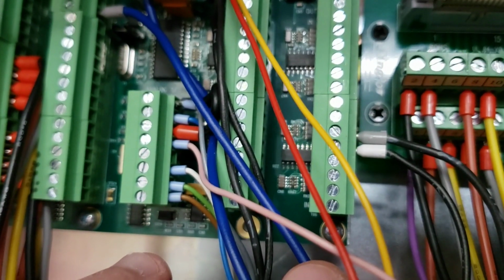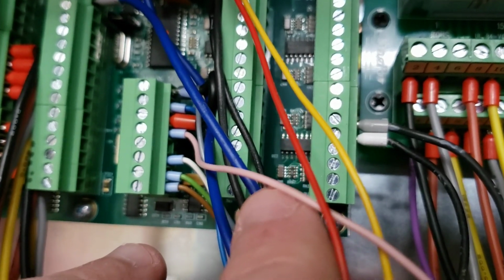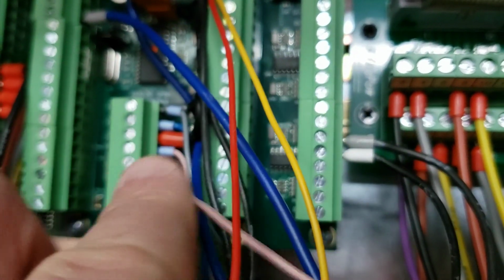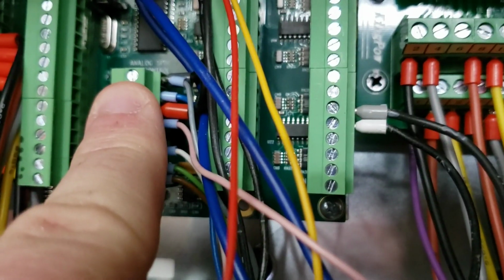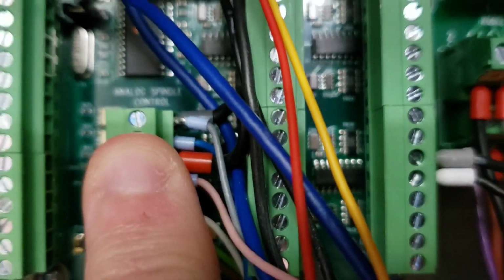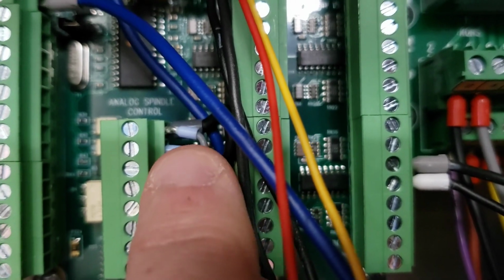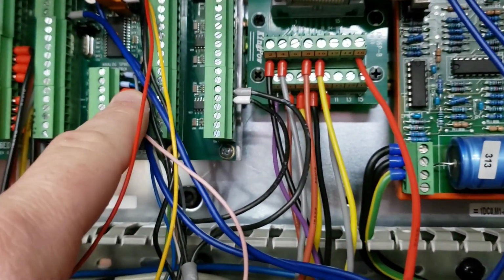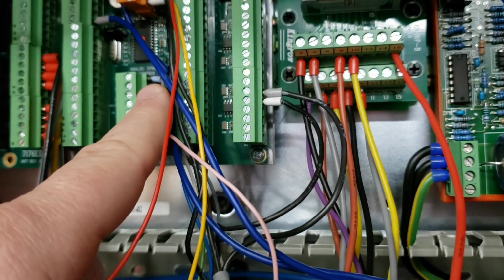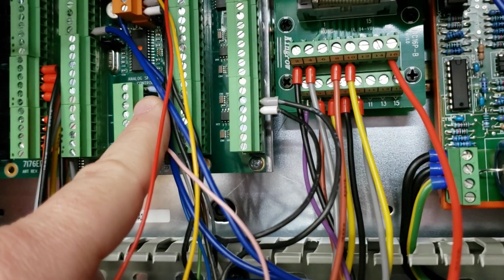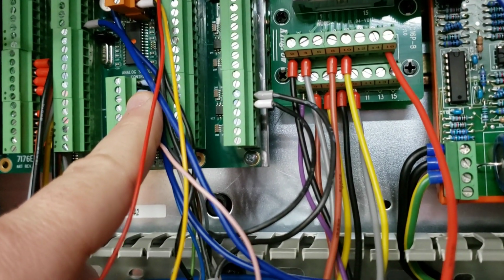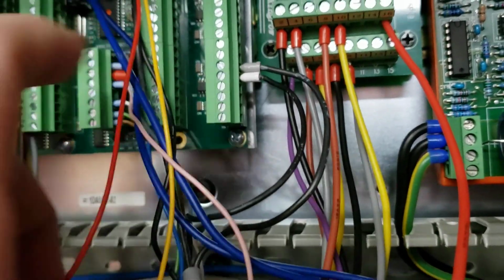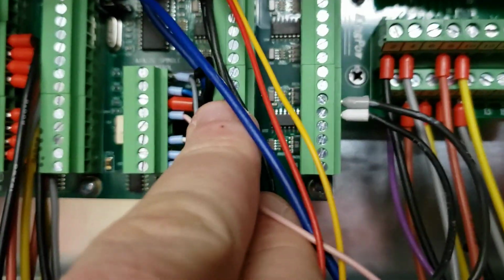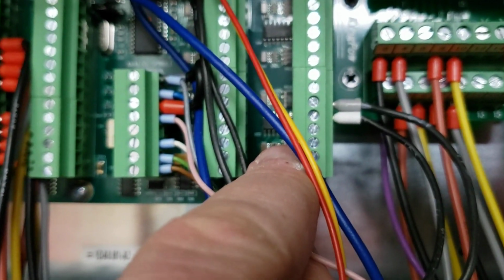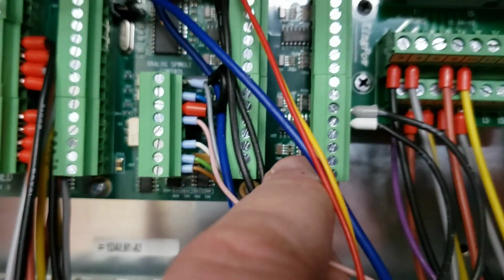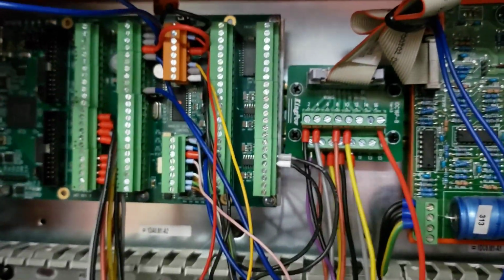I think I'm going to switch this a little bit and run number 20, which is the 20 volt, into here. And then I have the gray accessory, or the gray enable wire. Really, it's like an enable signal that'll spit out. I could put it into an input, and then if the VFD loses power, I could set up logic to stop the machine with that pin right there. So that's what I've got going on.